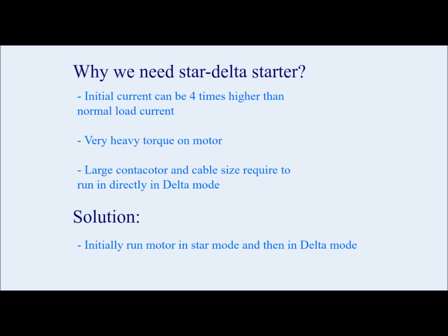If we run the motor directly in delta mode, initial current can be four times higher. It can cause very heavy torque on the motor and you need large contactor and cable size to run directly in delta mode. Solution will be to run initially in star mode and then change to the delta mode.